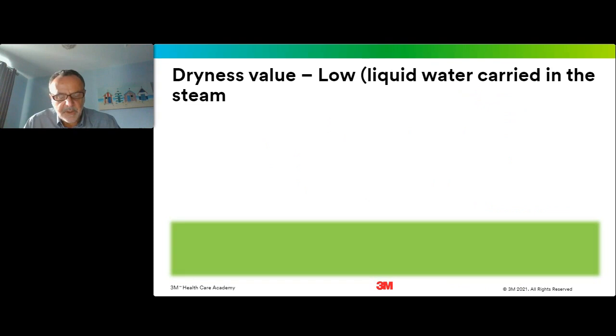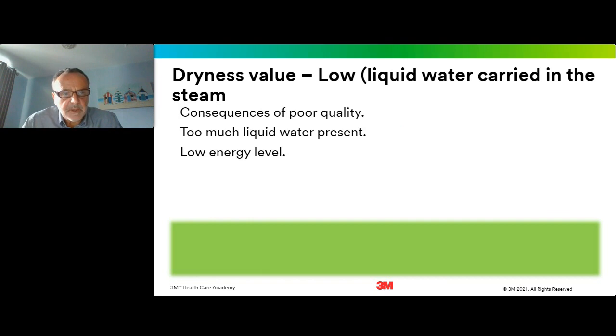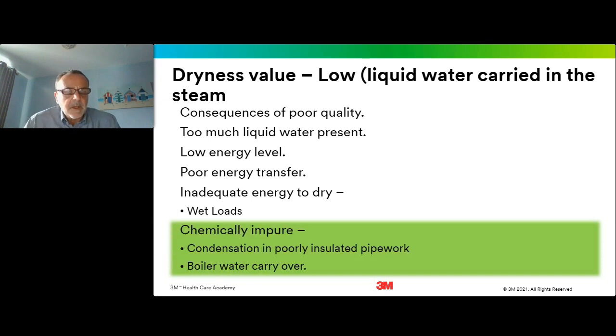So let's have a look at the dryness value and what impact this can have if it's too low. Well, if we have steam with a very low dryness fraction, then what this means is that there is too much liquid water present in it. And that means that for a given body of steam mixed with this water, it will have a low energy level, and therefore you will get poor energy transfer and therefore poor heating of your loads. And this in turn will have an impact on drying of your loads at the end of the cycle.